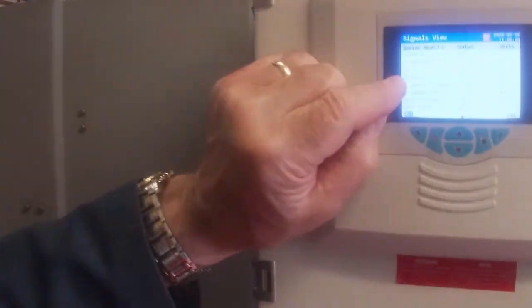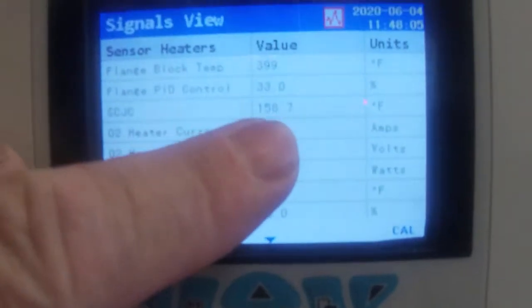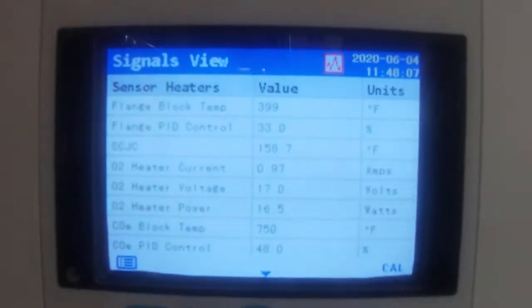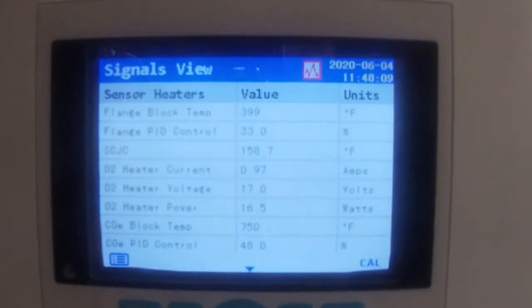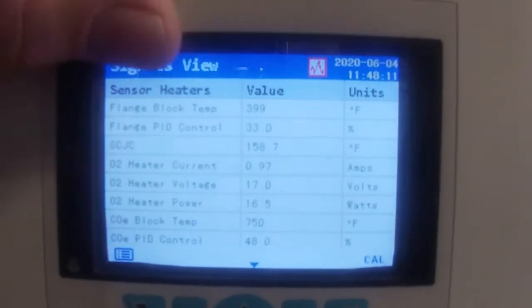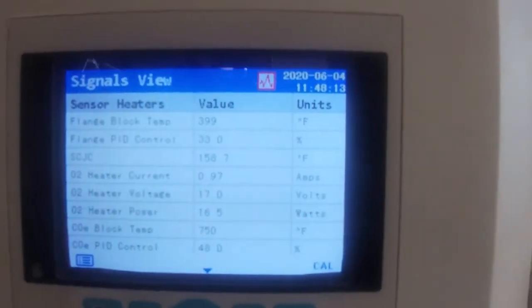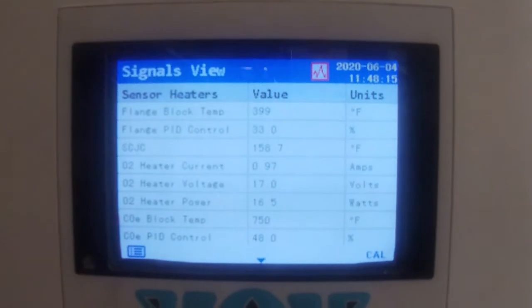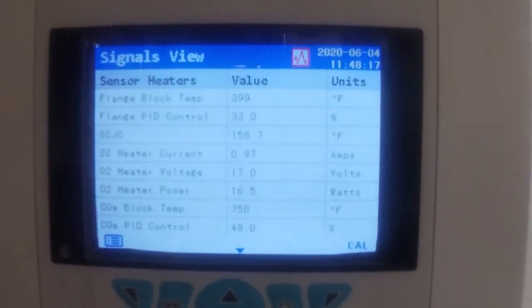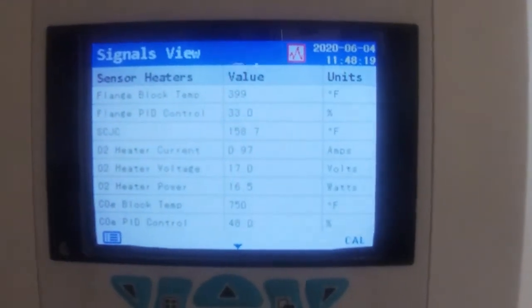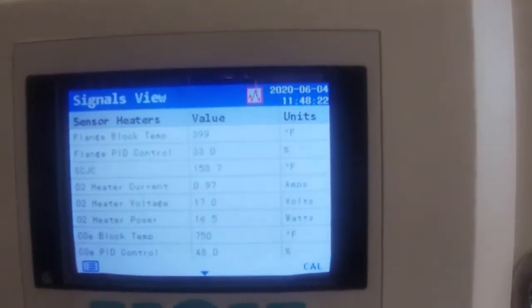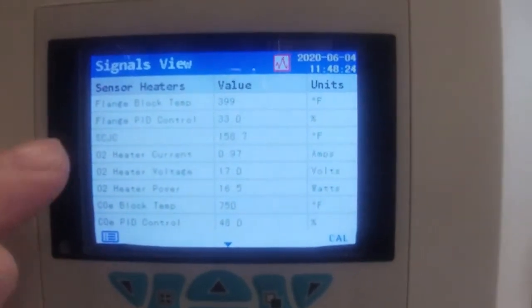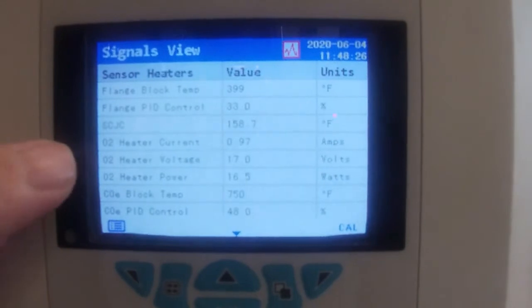So we needed to know what that was. And right now it's saying it's at 158.7 degrees Fahrenheit. And all that means is that that block up there is being controlled at 400, and then the next terminal block that is down from the block itself is sitting at 158.7. Okay, so it's warm, but it's not that hot. But it is telling you what that temperature is inside that block.